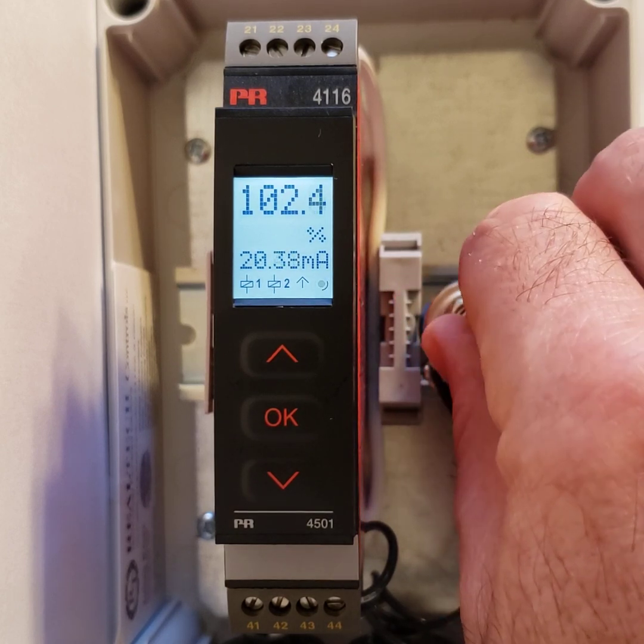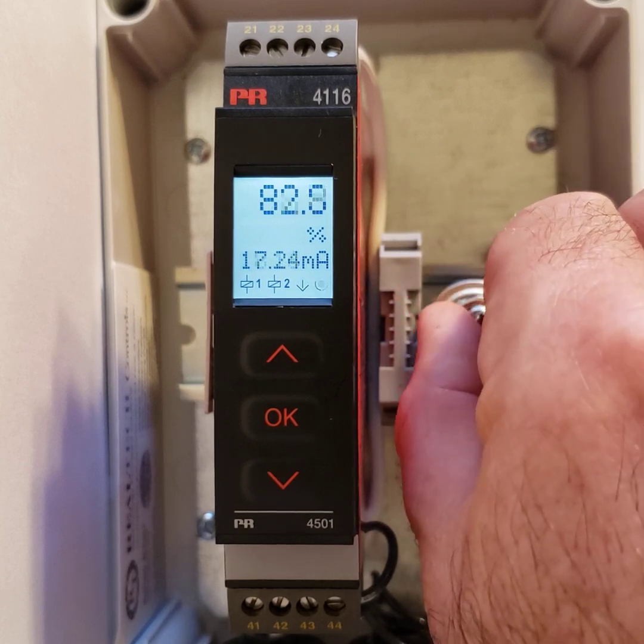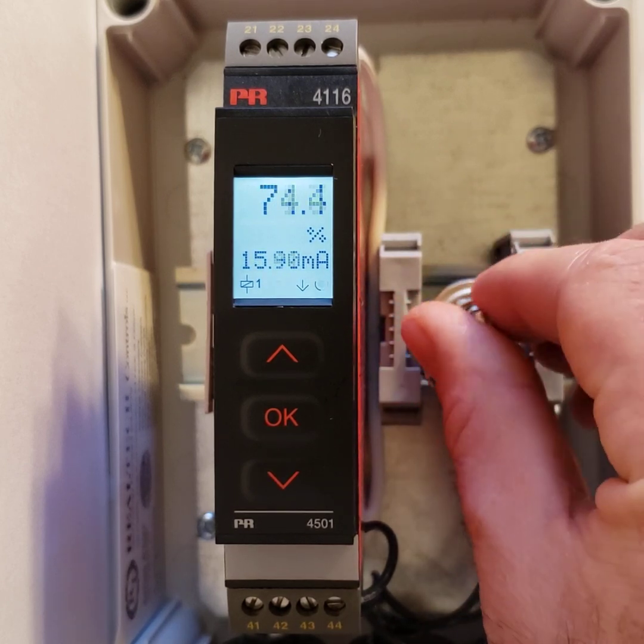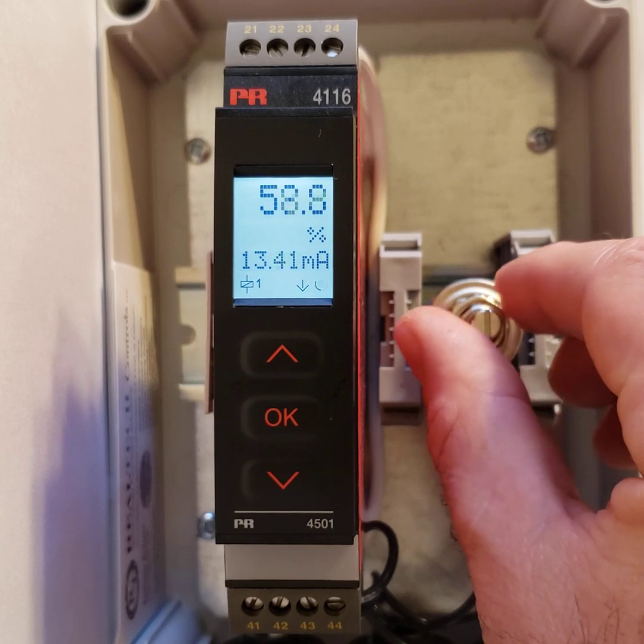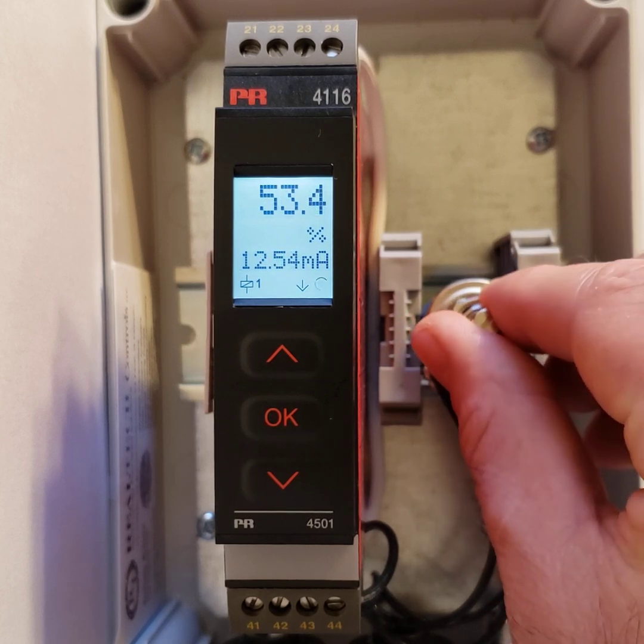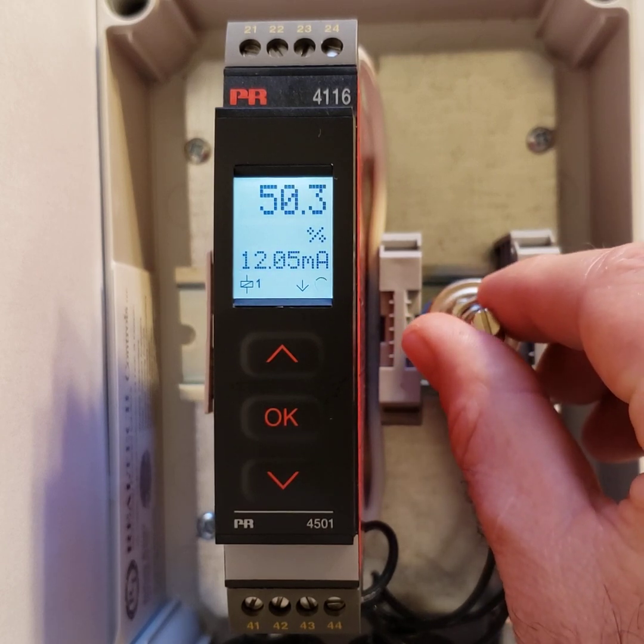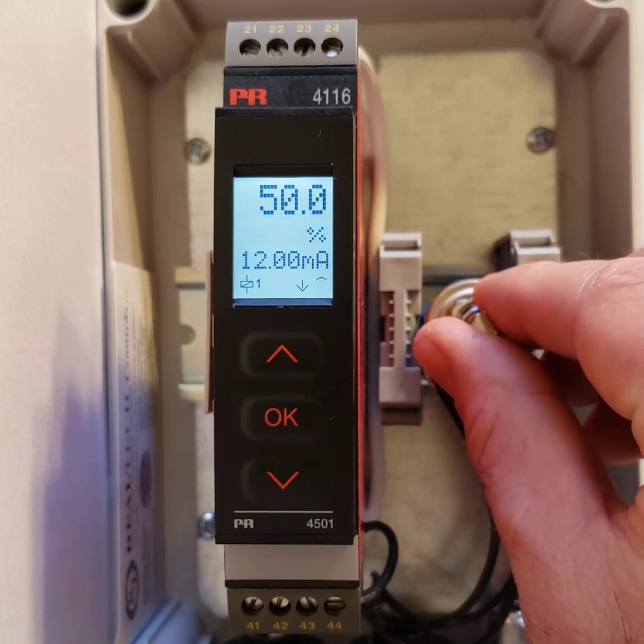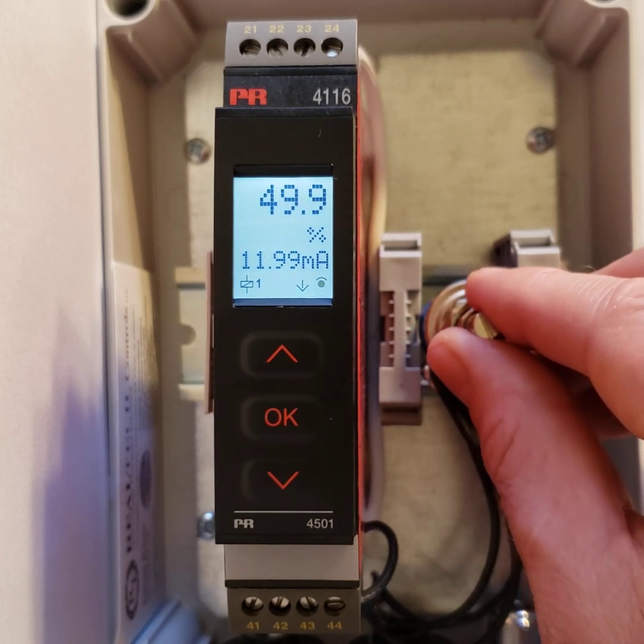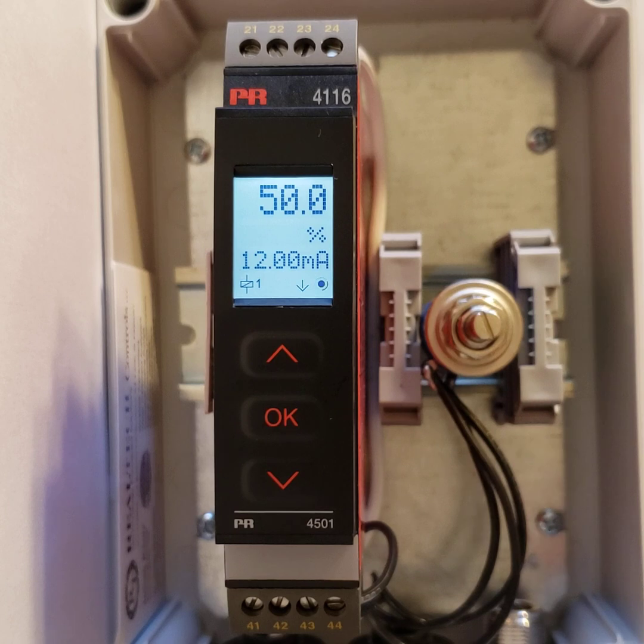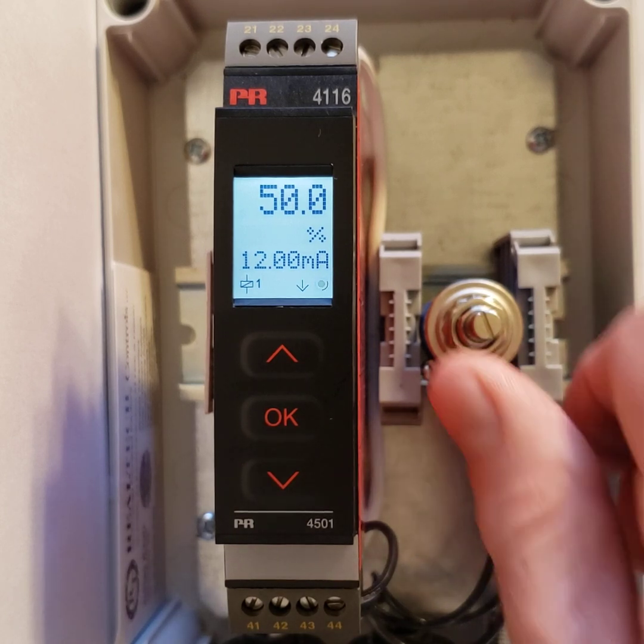So basically, this is a linear calibration too. And you'll see that if I do go to 12 milliamps or 50% of my pot, that's a very, very accurate linear device. And that scales it completely linear through your range. And you can calibrate any low and any high, basically.